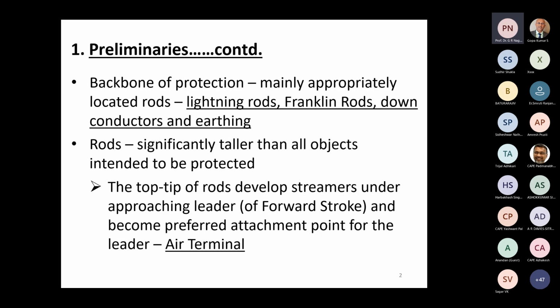And then for the Franklin rods or the lightning rods, the current has to flow down. So we have to provide a set of conductors which are aptly named down conductors, and these conductors must be earthed so that the fundamental process of current flowing into the earth from the cloud is completed. So this is known as the earthing system. We'll be covering only the principles of the whole lot, not going into the details, because the details of the down conductors and earthing particularly can be quite involved depending upon the configuration of the building and many other possible complications like structural discontinuities and things like that.